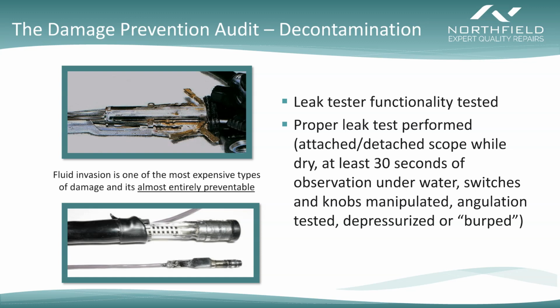Leak testing must be performed on every single scope, every single time, and we have to make sure the leak tester itself is working properly. We've had facilities say they leak test every time yet keep getting fluid invasion - we go in and check the leak tester, and it turns out their hose had a puncture in it. Your leak tester is not going to find any holes if it's not pushing air. So make sure your tester is functioning properly.